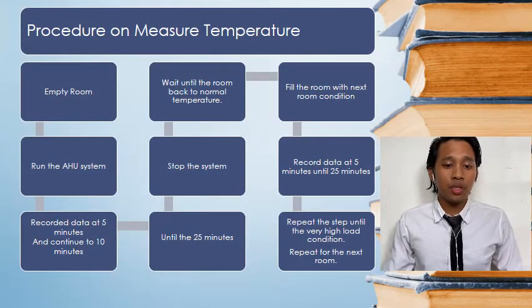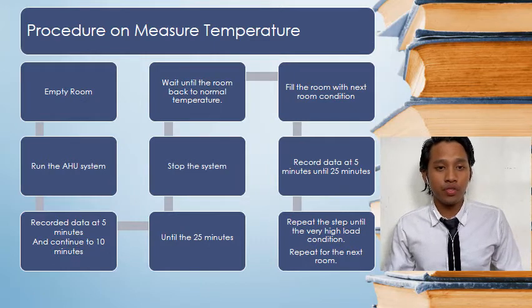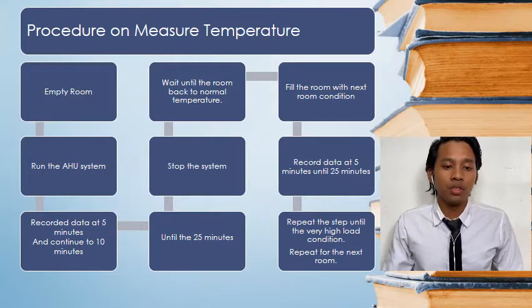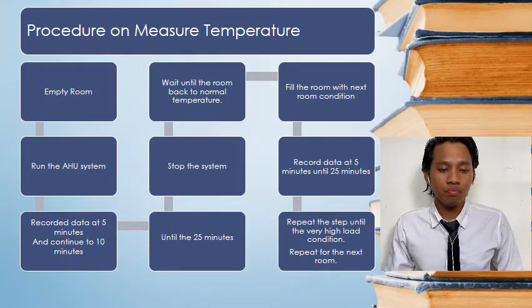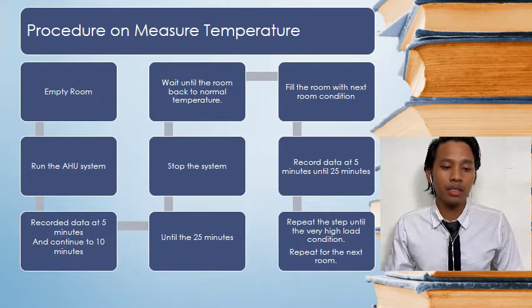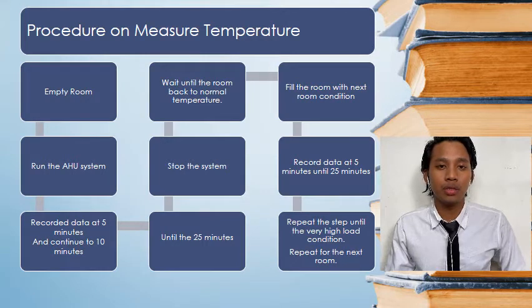So this is the procedure to measure the temperature of each room in a 3-room HVAC technology industrial lab. Firstly, this is just an example. For the first room, the condition is an empty room, which is a very low load condition. With the empty room, we run the HVAC system, and after 5 minutes, record the data. Then at the next 5 minutes, which is 10 minutes, we record the data, until 25 minutes. Then stop the system. After stopping the system, wait until the room is back to the normal temperature.